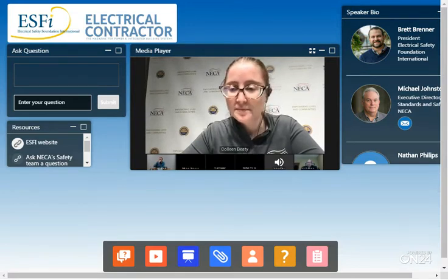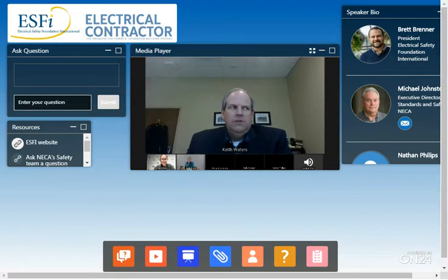Colleen, I'll take this one. Both GFCIs and AFCIs do have internal MOVs that protect the devices. However, the additional protection that a type 1 or type 2 SPD provides will increase protection from higher levels of surges, even beyond what those products are required to handle within their individual product standards. So they help protect those devices at a level even higher than what they're designed to protect themselves.